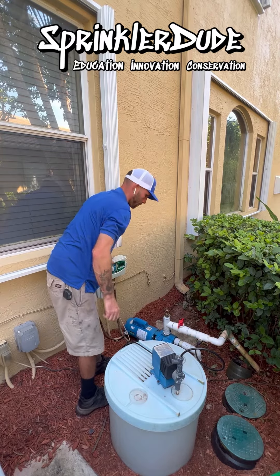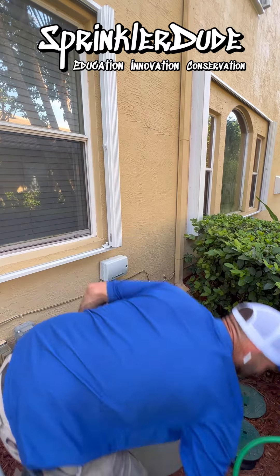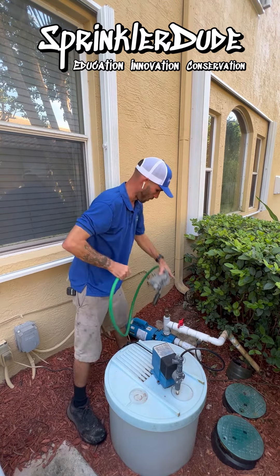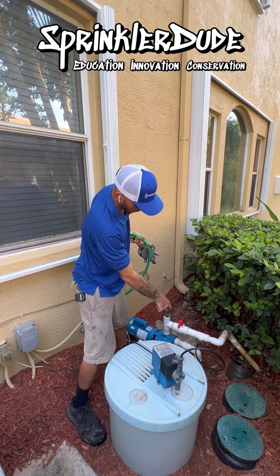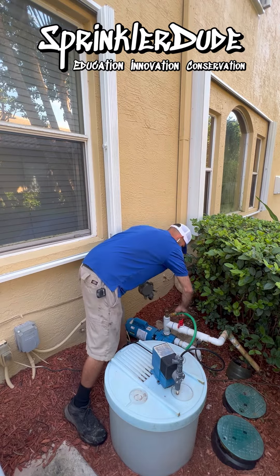We're going to need to prime this pump. So we'll shut that down and we'll grab our guzzler. With the ball valve closed to the field, we're only working with the pump itself and the check valve on the incoming line.